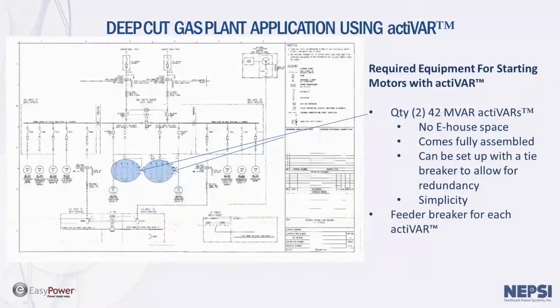If we were to look at an actiVAR solution in this case, we would replace those 7 reduced voltage soft starts with just standard across the line starters. So there's a standard 4 across the line starters here, plus the 3 over here, and we would replace the 2 drives here also with across the line starters and include 2 actiVAR systems. In this case, those motors were quite large, so the actiVAR system is actually 42 megavars each, so a quantity of 2 42 megavar actiVARs would be required. But these 2 actiVARs would accomplish what the 7 soft starts and 2 VFD drive starters accomplished with just 2 devices. We could also add tie breakers to the actiVARs here to provide redundancy.